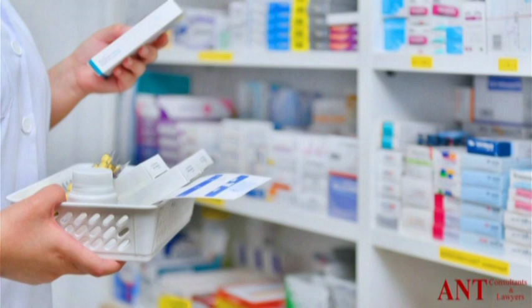In case the dossier is complete and valid, a meeting of its consultation council for issuance of medical equipment import permit will be held to review. The import permit will only be issued if there is no more requirement for modification or addition of import dossier from the council. The validity of the import permit is until the validity of the letter of authorization and up to 1 year from the date of signature and issuance.